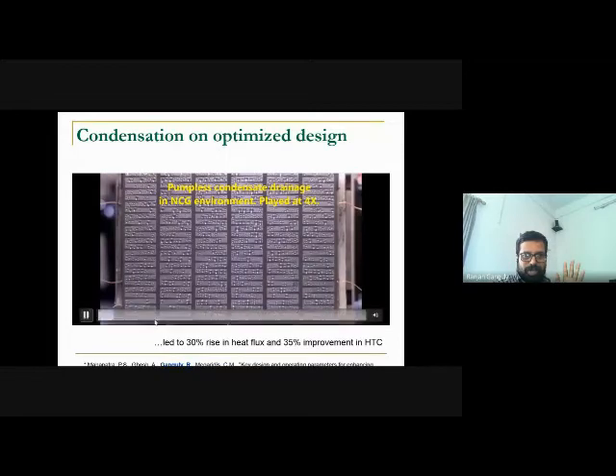The liquid drips down at regular intervals from intended spots. Most importantly, this led to a 30% increase in heat flux and 35% improvement in heat transfer coefficient. Imagine a condenser in a power plant rejecting 300 megawatts of heat. A 30% improvement in heat flux means you can make the surface 30% smaller, which is a better engineering design.